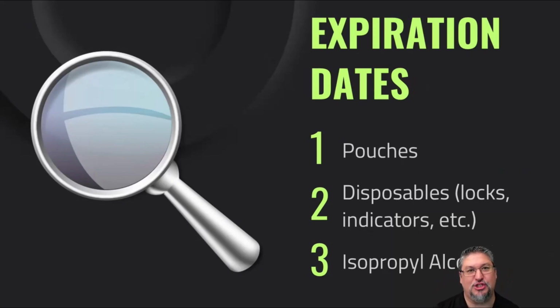So you have to have some way to track when these pouches expire. My recommendation is to keep it in the box or find a manufacturer that actually has the expiration date on the individual pouches. Some of them do. They're probably the ones that are a little more expensive, because that kind of foresight usually means there's more expense involved. But the pouches and the expiration dates are very easy for them to spot. If it's not in a box, then they'll say, when do these expire? And if you can't answer, there's a finding.